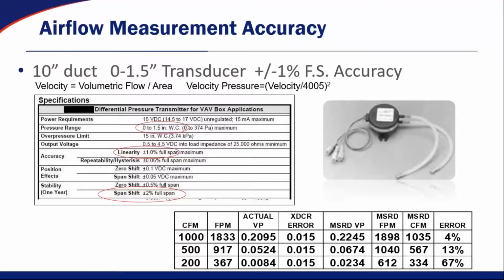And just like the same calculation, if I try to get a 5-to-1 turndown, going from 1,000 to 200 CFM, again, my velocity drops to 367, and there's kind of an industry standard of around 450 feet per minute that is really where the bottom of measurement capacity is. So this is really stretching it anyway, but for the benefit of the calculation, we'll go through it. So at 200 CFM, my velocity is 367. My actual velocity pressure, which is 367 divided by 4,005 squared, is 0.0084.